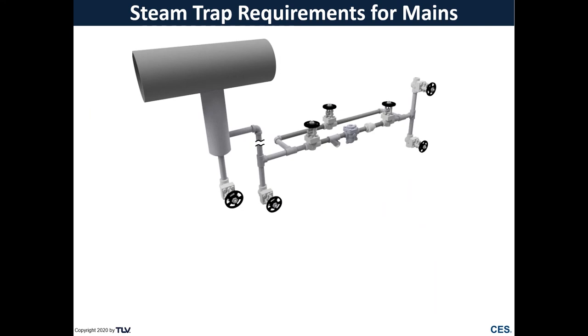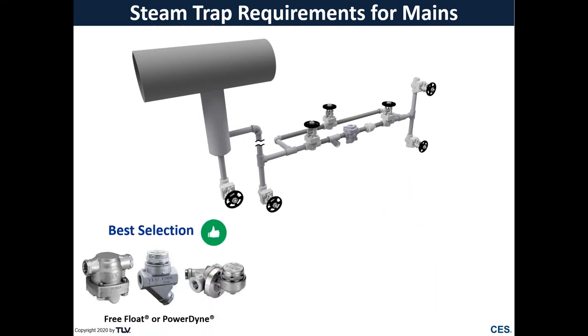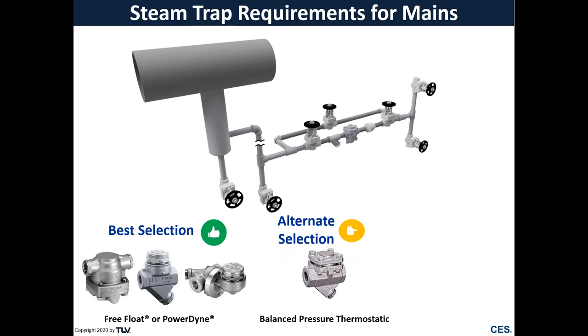So for steam trap selections, the best selections are going to be a mechanical style trap, such as the TLV free float, or a thermodynamic trap, like our Powerdyne. Alternatively, you could use a balanced pressure thermostatic trap, but we would definitely want to avoid using a bimetallic trap because of its tendency to back up large volumes of condensate.